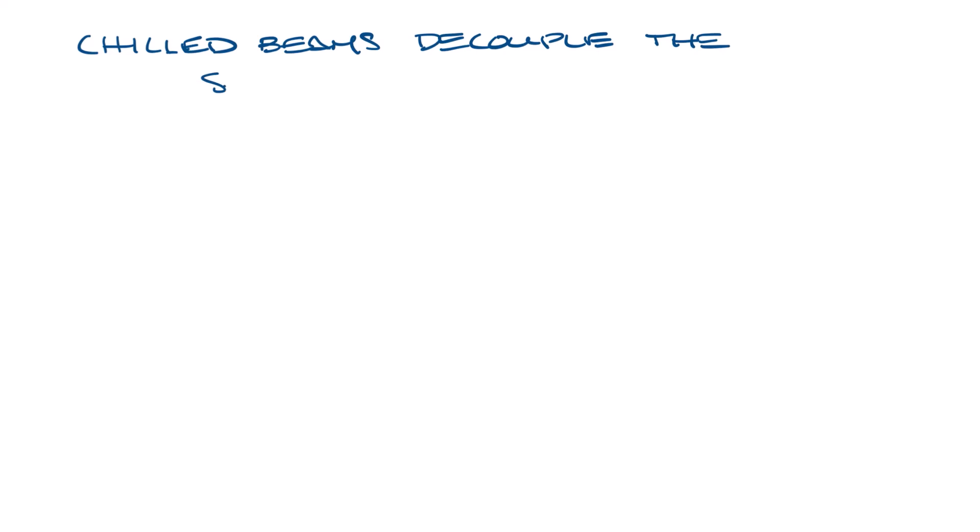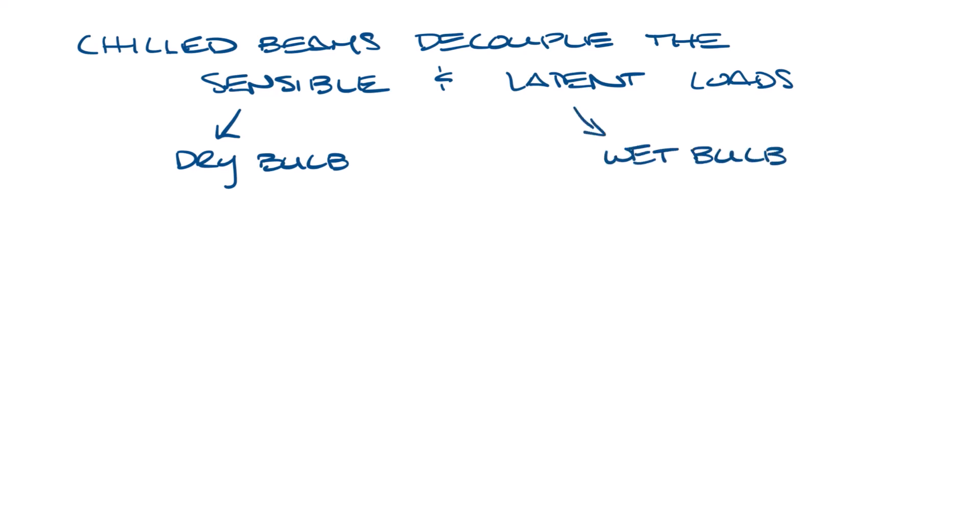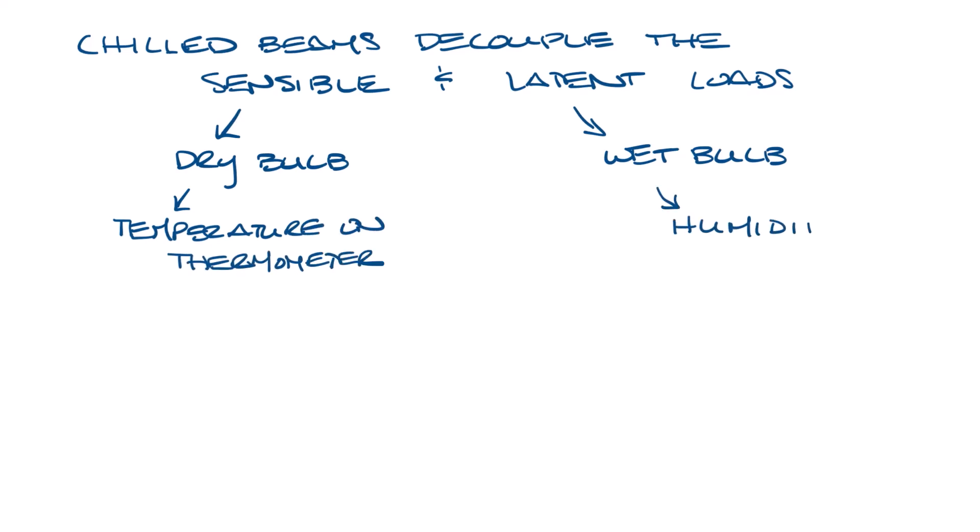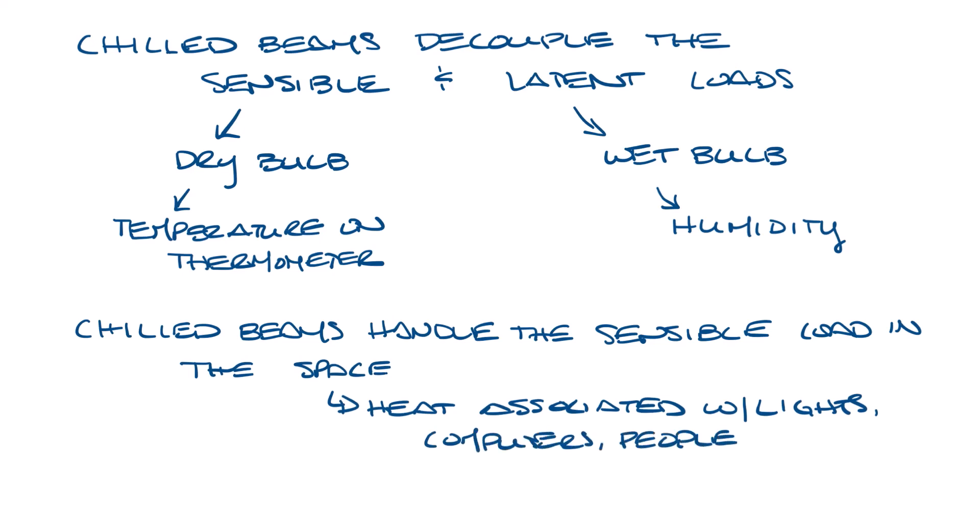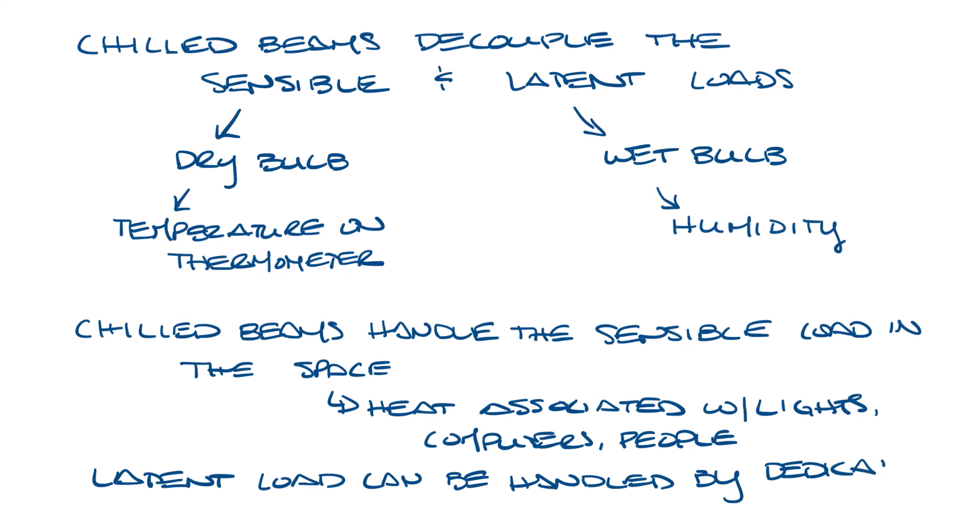Chilled beams decouple the sensible and latent load in the space. The sensible load refers to the dry bulb temperature of the building and the latent load refers to the wet bulb temperature of the building. You can think of it as the sensible load referring to the temperature on the thermometer and the latent load referring to the humidity. Chilled beams allow you to decouple the sensible and latent loads. The chilled beam handles the sensible load in the space. They take care of the heat associated with the lights, computers, and people in the space. And then the latent load is typically handled by a dedicated outdoor air system, a DOAS system, which I'll discuss in future videos.